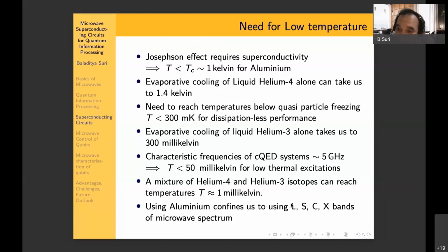But is 1 Kelvin enough? No. We need to actually reach far below 1 Kelvin, because superconductivity is a sudden transition as far as the resistivity of the metal is concerned. But if you go down, there are other aspects of the superconductor, like quasi-particle poisoning, etc., which have a slower dependence. So to counter those, we need to actually go to much lower temperatures, say of the order of less than 300 millikelvin. Now, those are temperatures that we cannot reach using helium-4. So we need to immediately bring in helium-3. But helium-3 is extremely expensive. So say a few liters of helium-3 will cost you about $50,000. Okay, so that's how expensive it is.